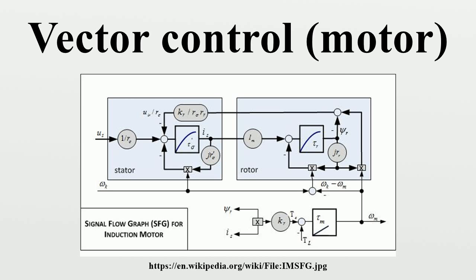Technical overview. Overview of key competing VFD control platforms. While the analysis of AC drive controls can be technically quite involved, such analysis invariably starts with modeling of the drive motor circuit involved along the lines of accompanying signal flow graph and equations. In vector control, an AC induction or synchronous motor is controlled under all operating conditions like a separately excited DC motor.